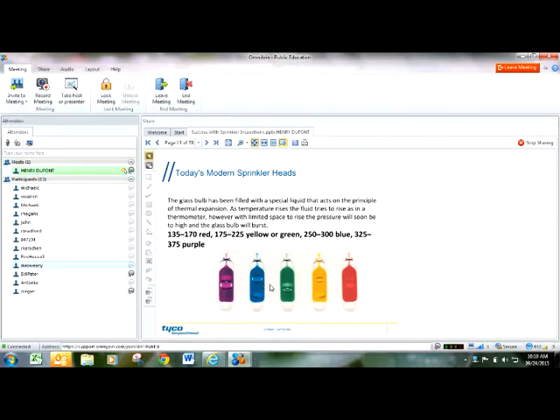And you might ask, well, why would you want sprinkler heads to go off at different temperatures? Your standard sprinkler head that you have in most buildings is going to be this red one. It's going to go off between 135 and 170 degrees. However, if you have a sprinkler head in a hot kitchen, you might want to use a sprinkler head that has a higher temperature. Or if you have a sprinkler head that's located at the roof level of a warehouse where it gets hot, you're going to want a sprinkler head that's up in the 212 to 286 degree range. That explains what the different colors represent.